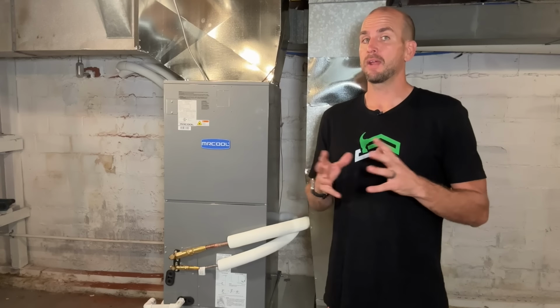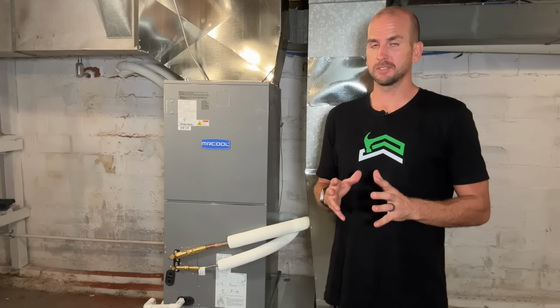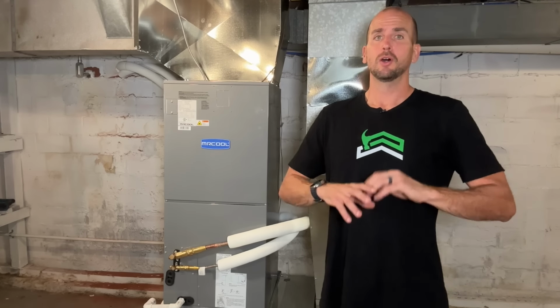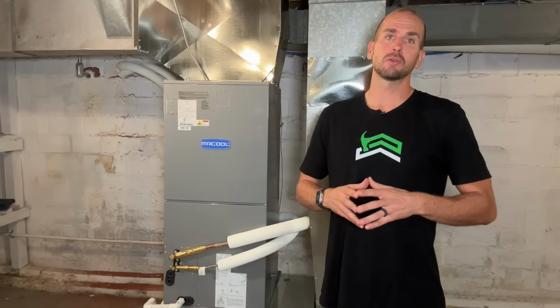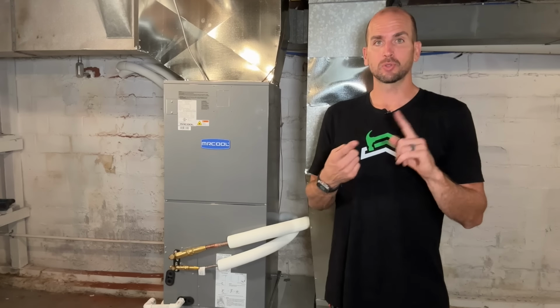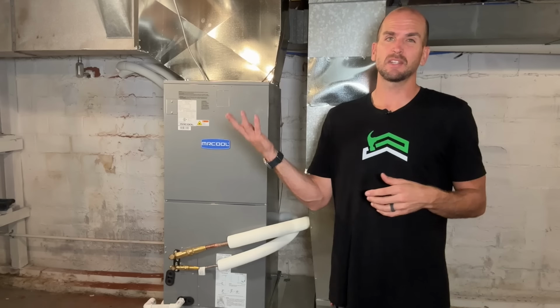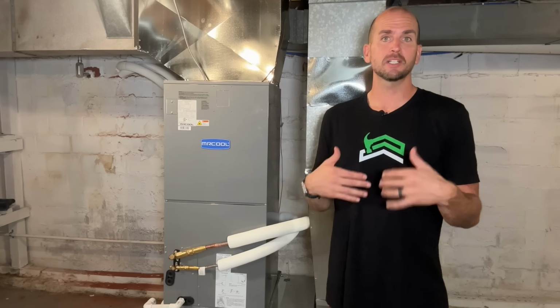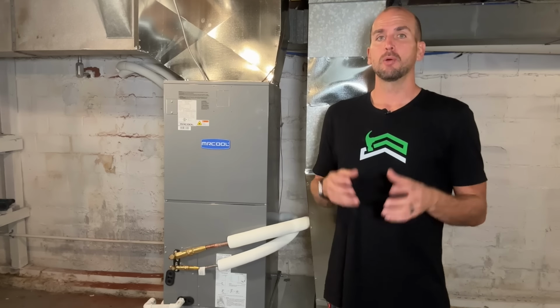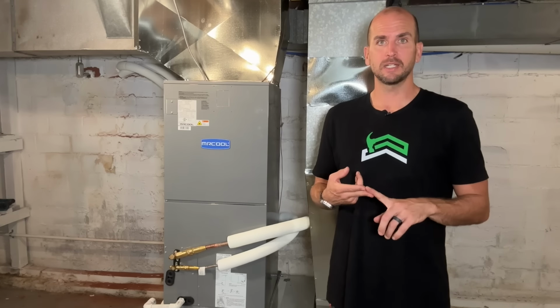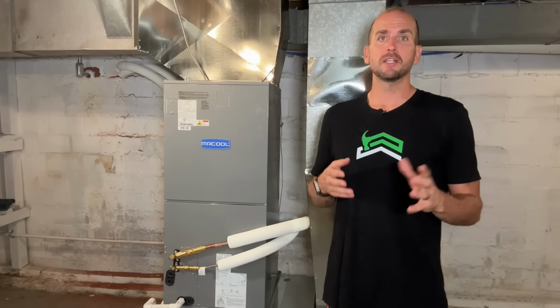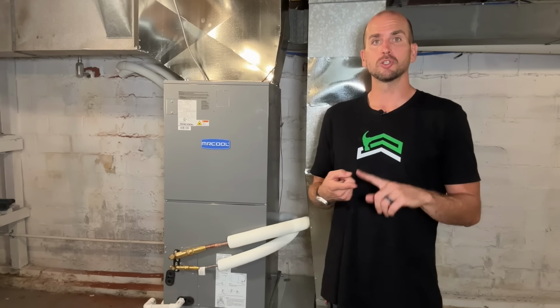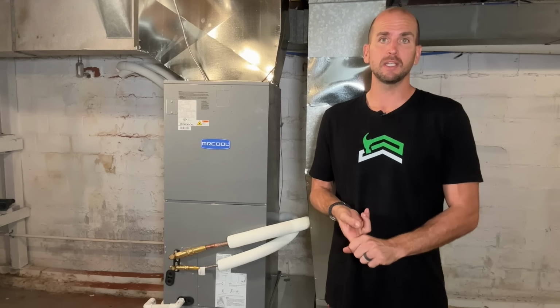So at this time we have everything connected up and we can actually test out the system, the moment of truth. Hopefully everything's connected together correctly and we're able to get both cooling and heating. The nice thing is it's 75 degrees Fahrenheit today, so I can actually test out the full system. What you want to do is make sure both of your disconnects are set in the on position and then go over to your breaker box and turn on your 15 amp and your 50 amp breaker.